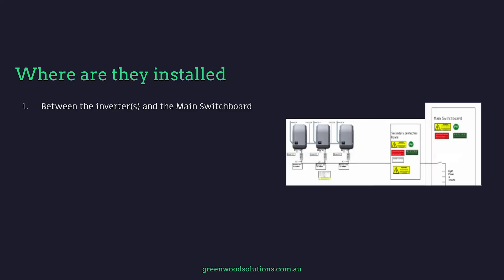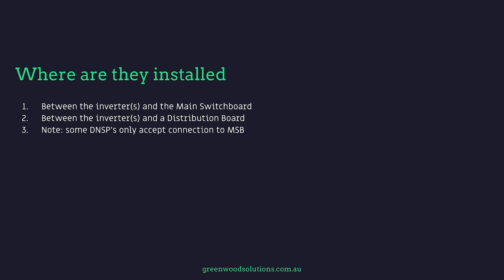Where are the secondary protection boards actually installed? Between the inverters and the main switch board in most cases, or between the inverters and a distribution board. Note that some DNSPs only accept a connection to the MSB. In most cases, secondary protection boards are installed fairly close to the MSB, and in fact some DNSPs stipulate it must always be connected to the main switch board. Others allow connection to a distribution board or secondary switch board.